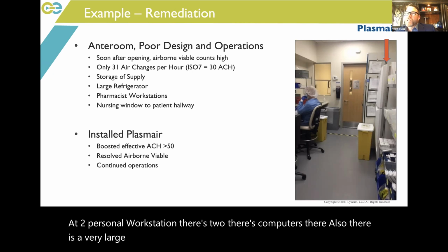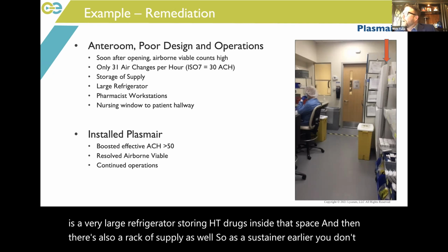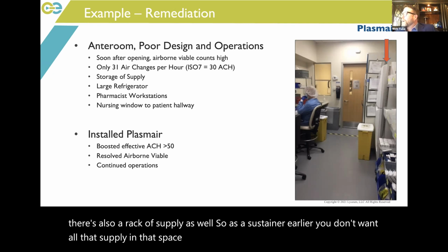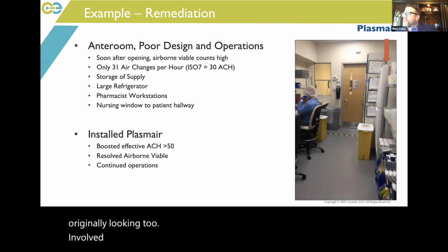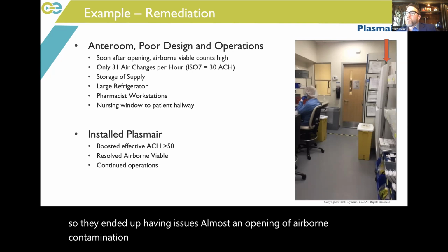So, as Seth was saying earlier, you don't want all that supply in that space, but this was a clean room that Grifols was originally looking to get involved with. They decided to go another direction because of costs. So they ended up having issues almost on opening of airborne contamination, very, very shortly after opening.